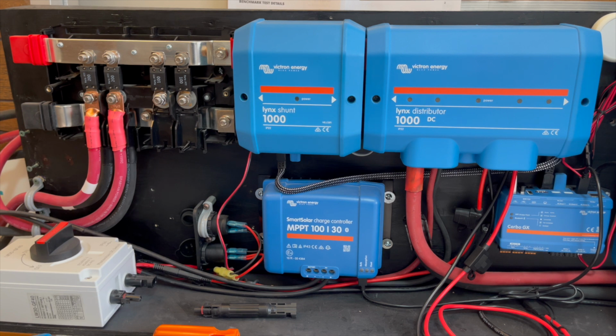But I've seen people saying, oh, number 4, number 3, okay. They have 10 or 20 or 15 feet of number 3 wire or number 4 wire going to their inverter or their solar system. And on top of that, because of the way they set up their equipment, one line is longer than the other. No. That's totally wrong.